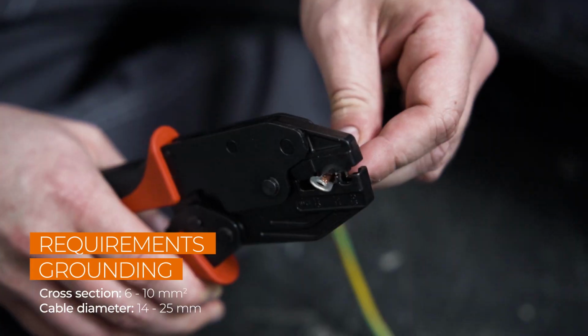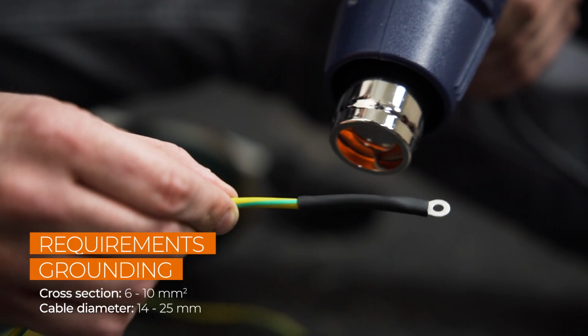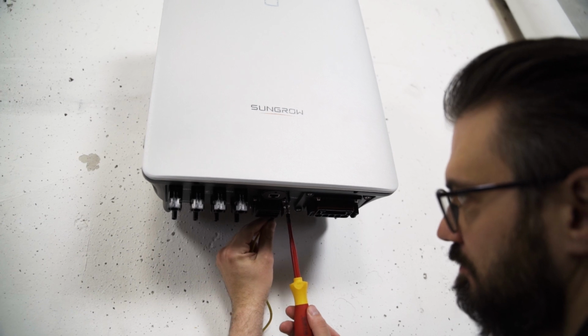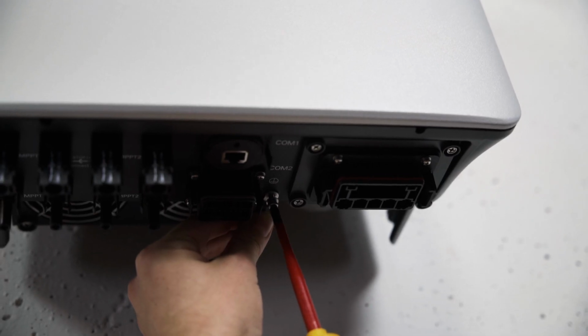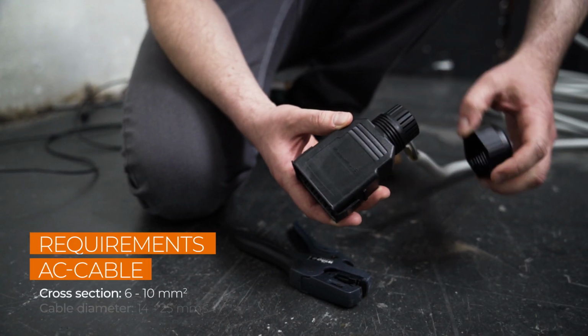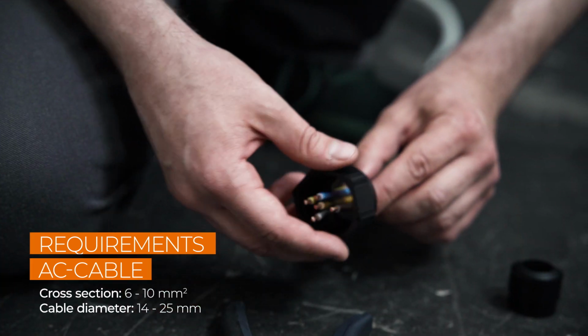Now let's connect the inverter to ground. There is a grounding terminal at the bottom of the inverter, connected to the general grounding of the house. We start with the AC plug. Because of our handy plugs, you don't have to open the inverter for installation.